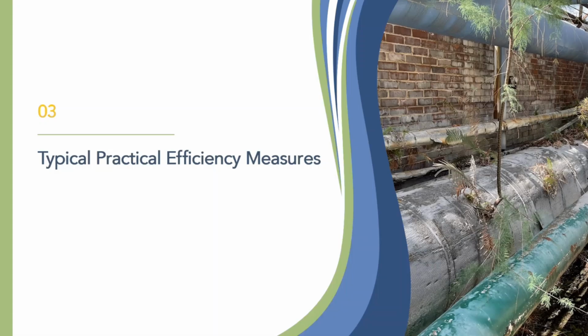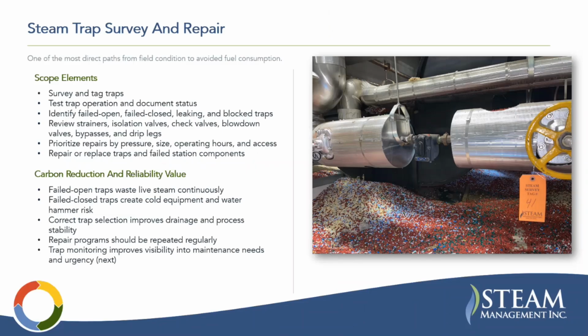All right, now we'll talk about some typical practical efficiency measures. Some of these I've talked about in other webinars, but they just can't be overstated. The first of which is steam trap survey and repairs. This is probably the most direct path from analyzing a field condition to avoiding fuel consumption or decarbonization. So you're going to survey and tag traps, test traps for operation and document status, identify failed open, failed closed, leaking, and blocked traps, review strainers, isolation valves, check valves, blowdown valves, bypasses, and drip legs.